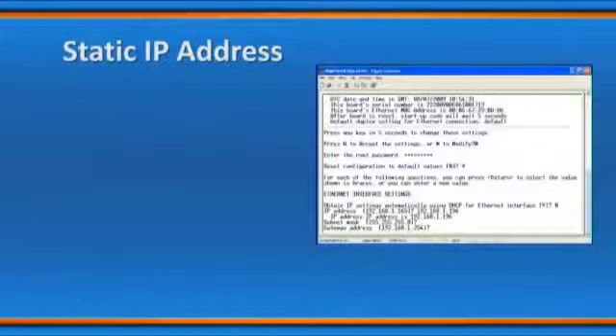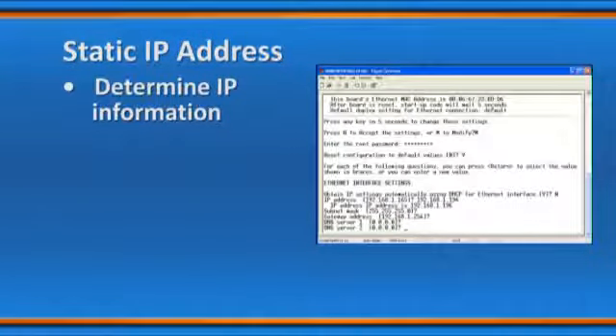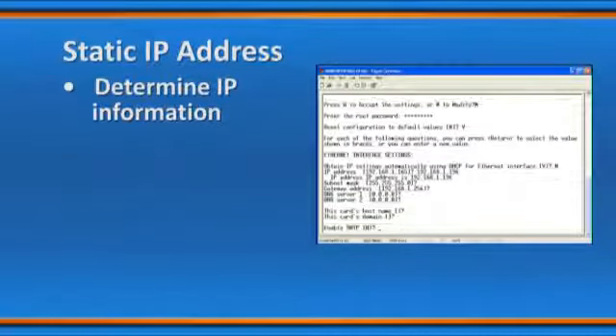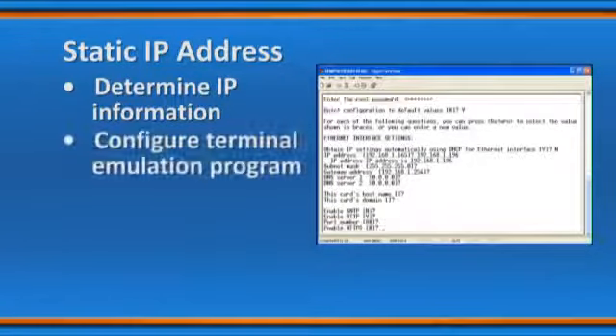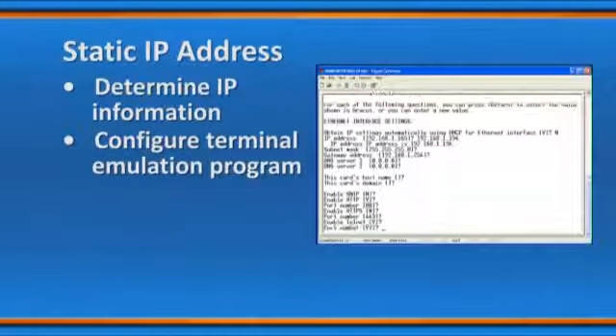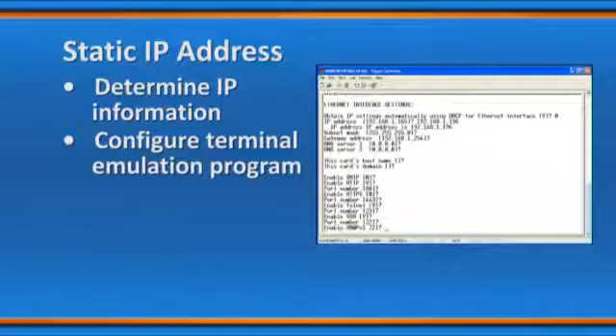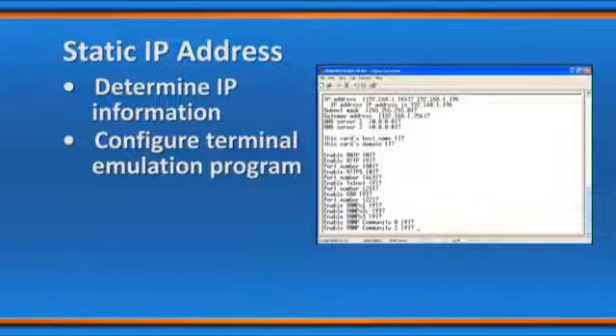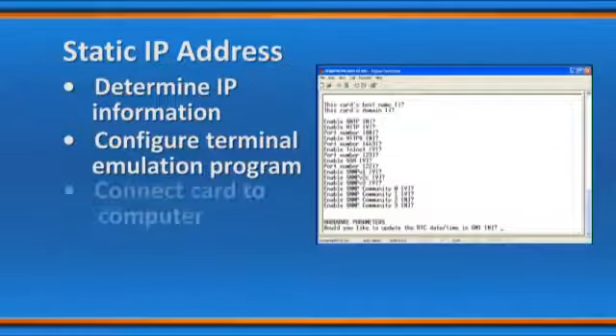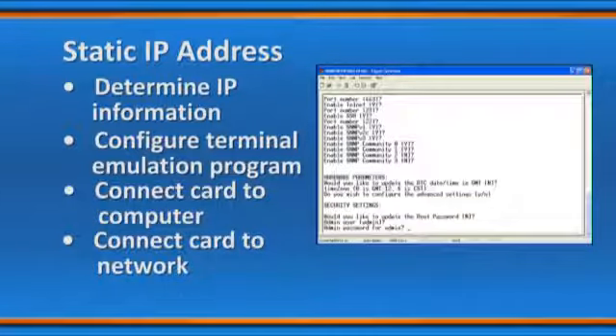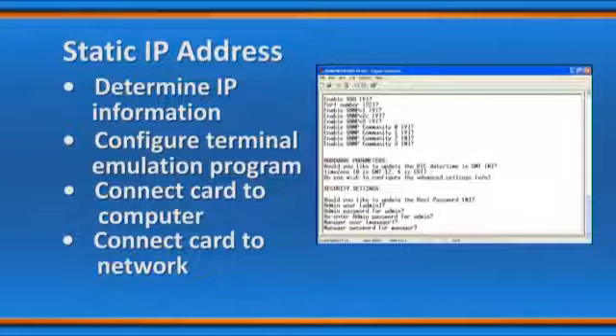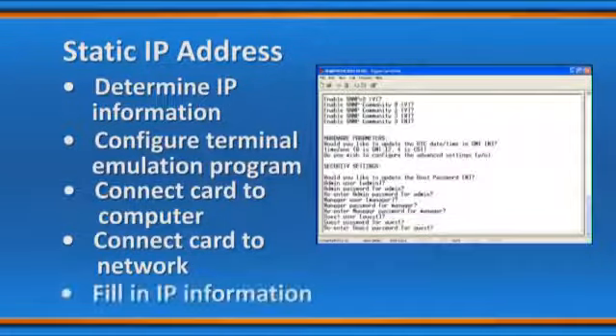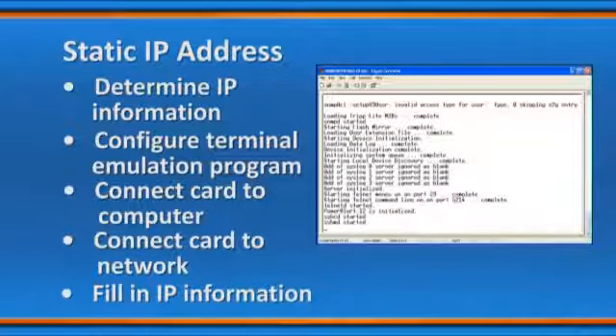If the network administrator determines the SNMP web card will use a static IP address, you'll first need to determine the desired IP address, gateway address, and subnet mask. Then, open a VT100-compatible terminal emulation program, such as HyperTerminal, which is bundled with Windows, on a computer with a DB9 serial port. Specify the parameters for the computer to communicate with the card. Use the included cable to connect the card to the computer. Connect a network cable from the Ethernet port on the card to a network jack. An initialization page will appear in the terminal emulation program. Fill in IP information. The card will save the settings and reboot. Disconnect the card from the computer.